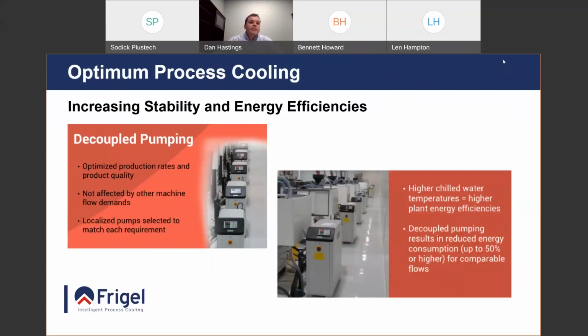All right, increasing stability and increasing energy efficiencies. If you are using a central chilled water system, it might be interesting to look at a portable chiller besides the press, if you have 1 or 2 machines or 1 or 2 molds that require a much lower temperature. Let's say you have 10 machines in your plant and 1 or 2 of them are running at 50-degree water, while the rest are running at 70 plus. Why lower the temperature of the whole central chiller system just to heat water up again for those other 8 machines when really you have to run that cold just to cover 2? Maybe a portable chiller at those 1 or 2 presses that need colder water might make sense. That way you have maybe a 2 or 3 5-ton chiller providing that colder water, while that bigger central chiller can run at a higher temperature much more efficiently and save energy.